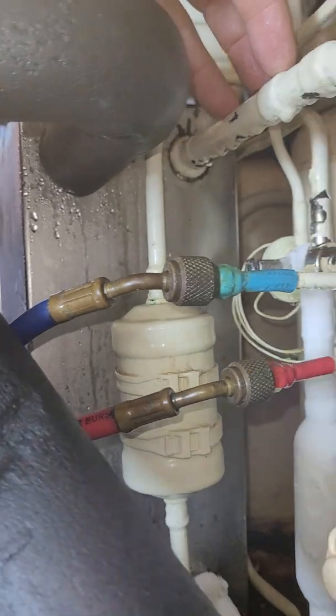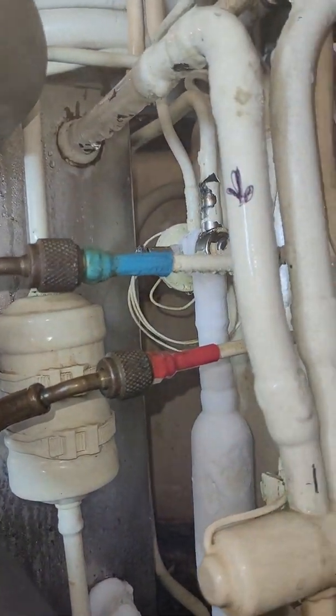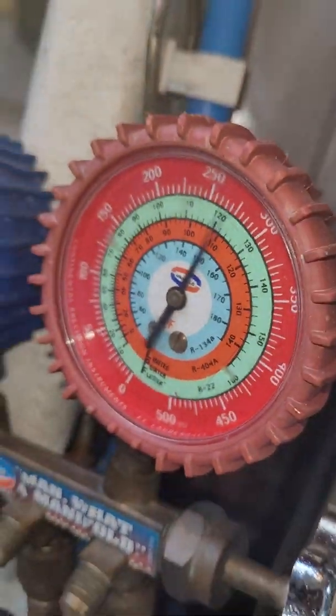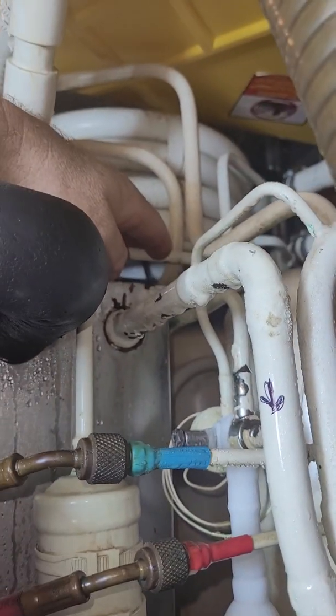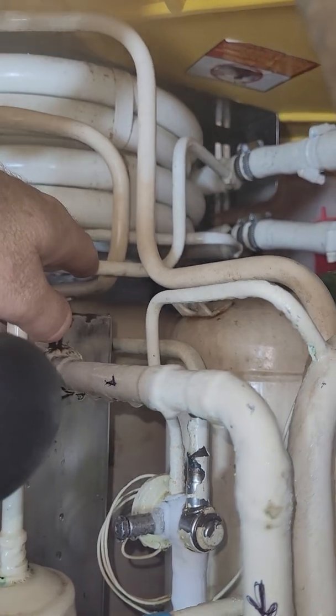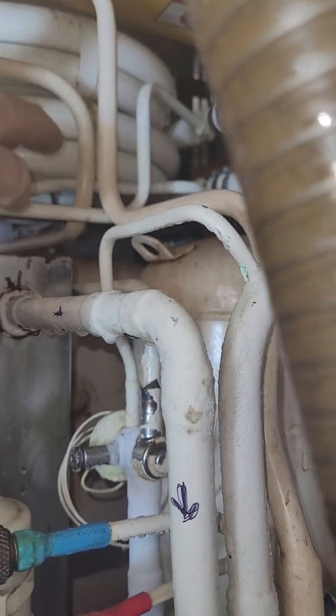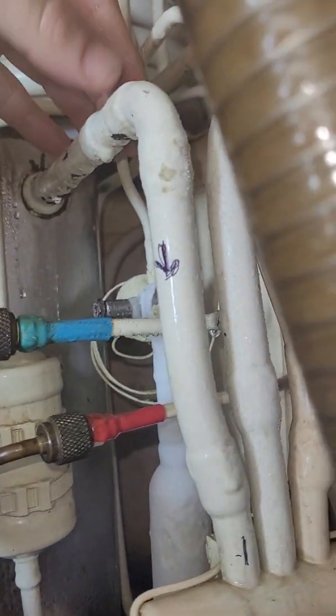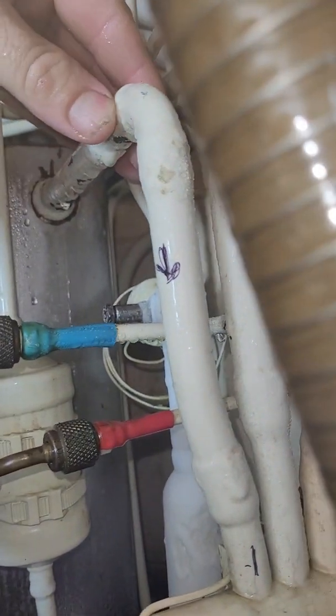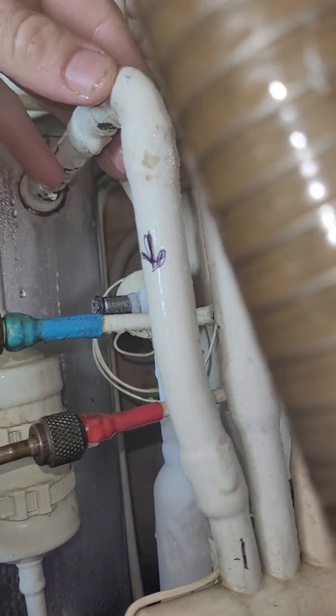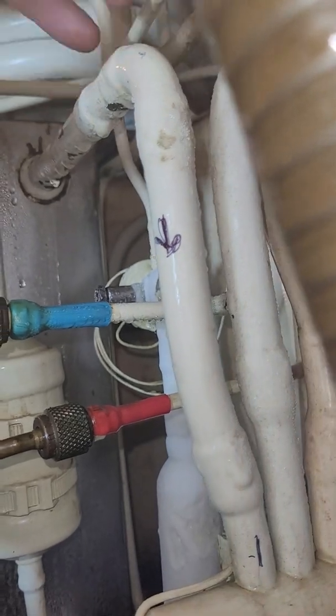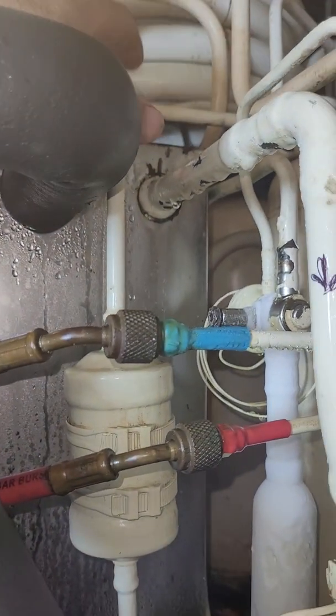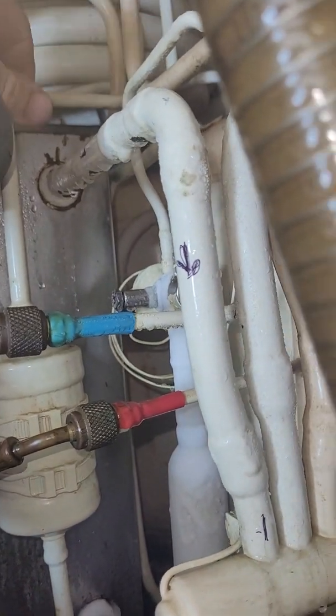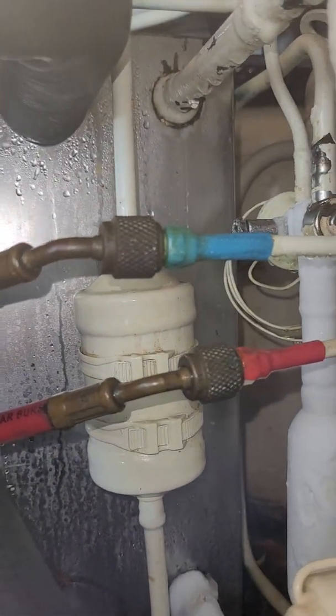And the saturation point of the gas is obviously very different with different pressures. At higher pressures, like we see here on the high side, we've got 275 psi right now, that saturation temperature is much higher. So this is subcooled liquid, and although it's subcooled, it may be warm to the touch, because it is subcooled relative to its saturation point. The same thing here, superheat may feel cool to the touch, but it is actually quite hot compared to the pressure. So superheat might feel cool to the touch, and subcool might feel warm to the touch. That's a little bit confusing, but it makes sense. And they're both looking quite alright, both superheat and subcool, and the amperage is also looking good.